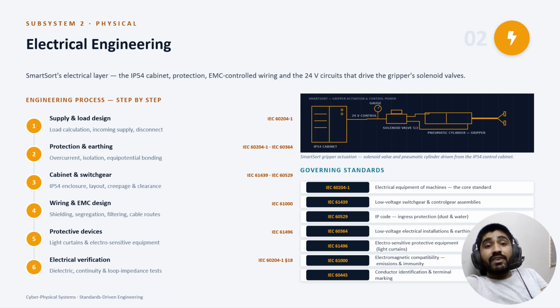Stage 6, verification, straight from clause 18 of IEC 60204. Protective bonding continuity, insulation resistance, and the dielectric test. Each recorded in a single report. The standard does not let you claim safety. It makes you measure it.